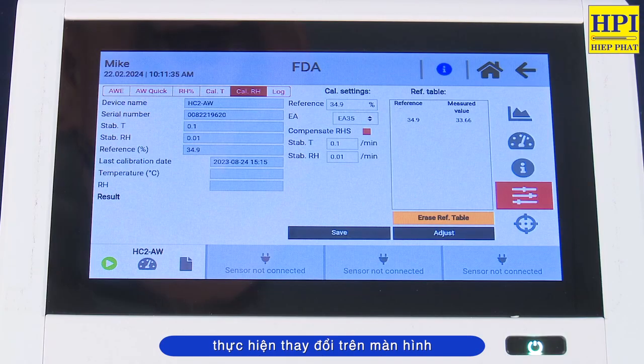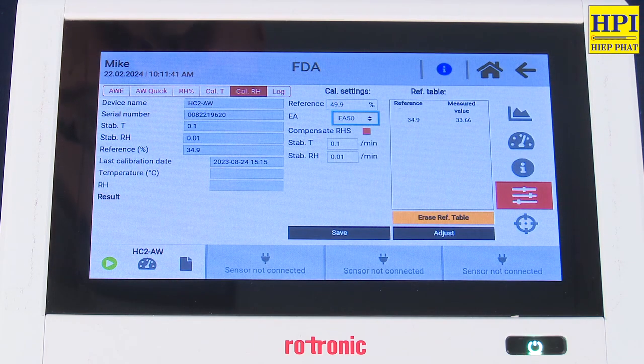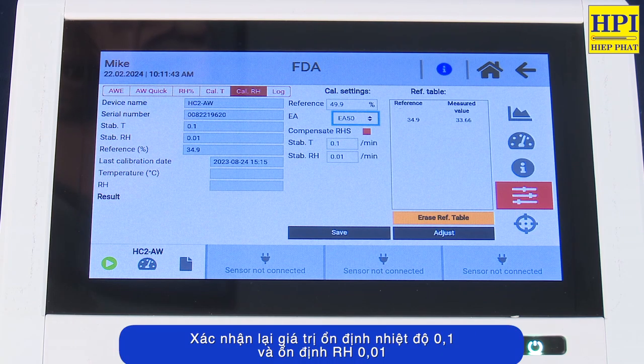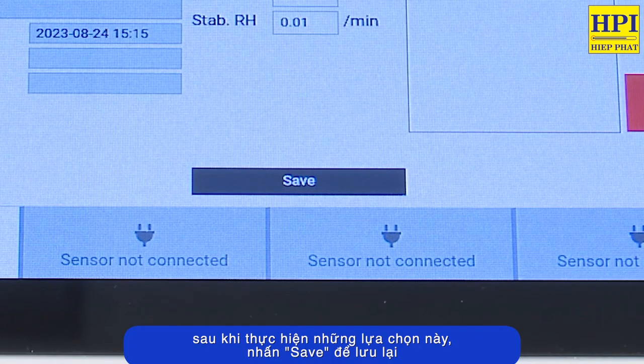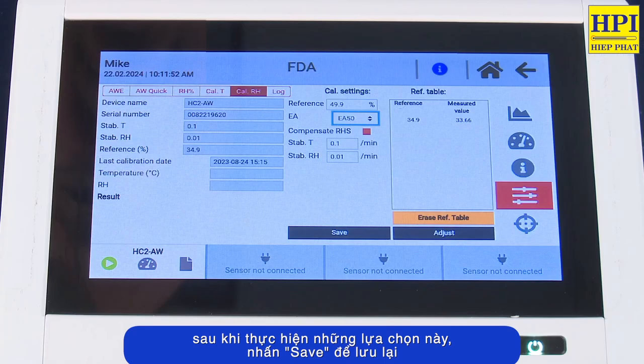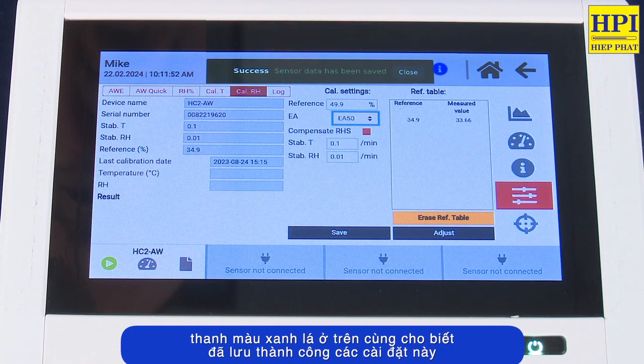Make the change on the screen under the Cal settings drop-down menu. We will move to 50%, verifying our temperature stability and RH stability are at 0.1 and 0.01 respectively. Once we've made these selections, we want to save. The green bar at the top indicates we've successfully saved these settings.